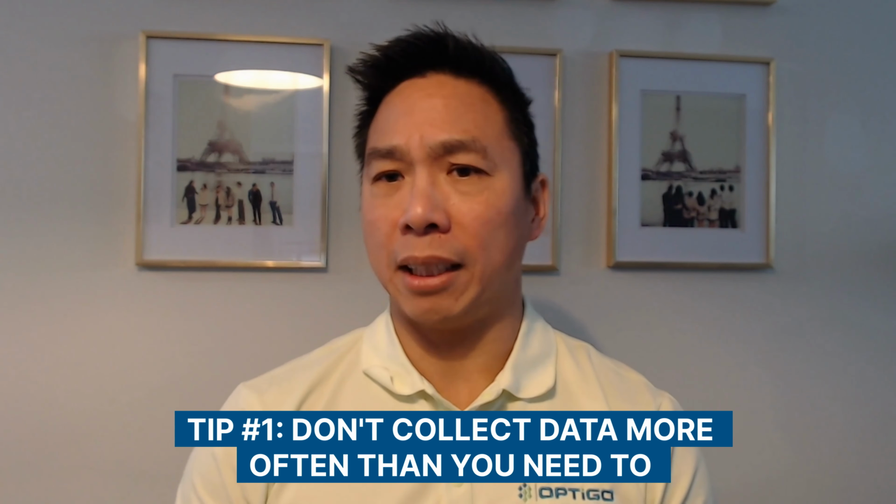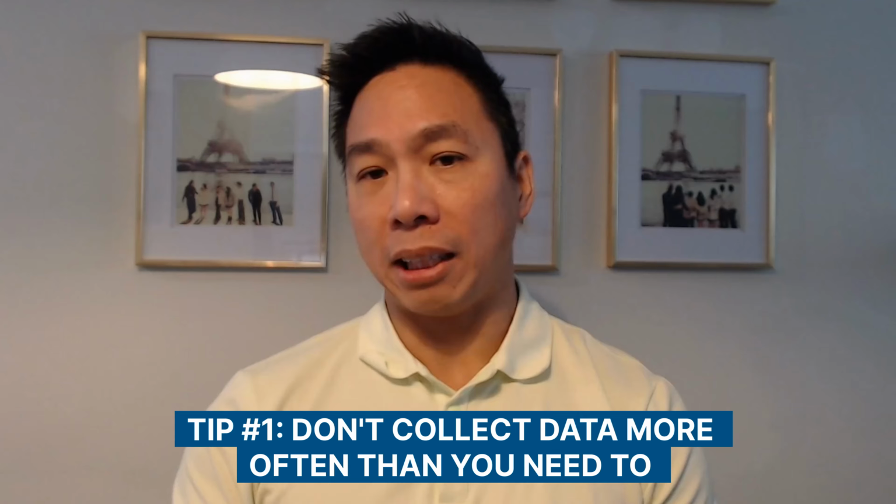You go into these large BACnet systems, these large building automation systems, and you say, I'm going to collect every point every 5 seconds. You will choke the system. You will run out of storage room, you run out of CPU, you will create bottlenecks where you don't expect them to be created. So I think it's a balance between that future growth, knowing that there's some data that it would be valuable for you to collect now that you can leverage in the future, but also balancing what you need now. So don't collect data more often than you need to, maybe slightly more, but not significantly more. By reducing that burden on the system, you can create space and margin in your system to do other things.